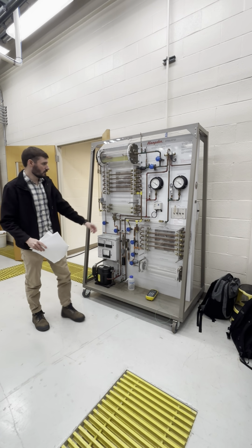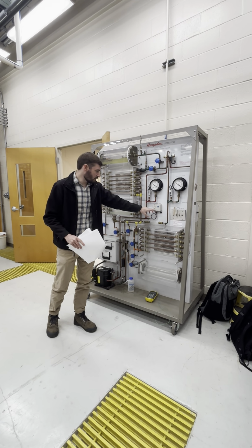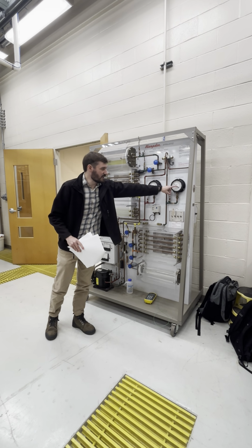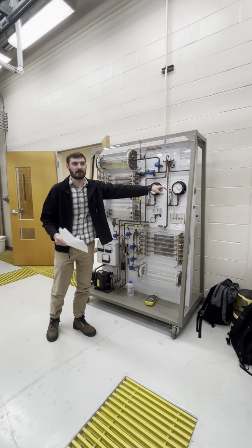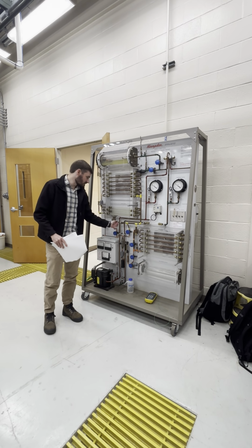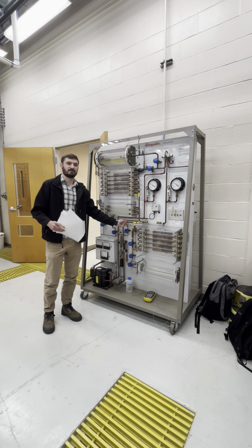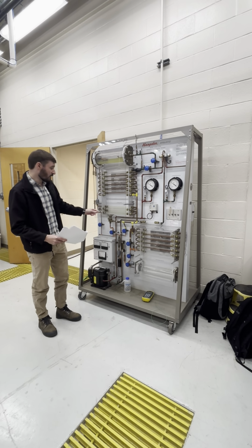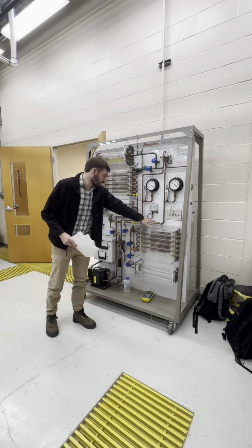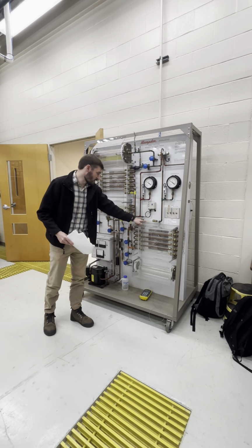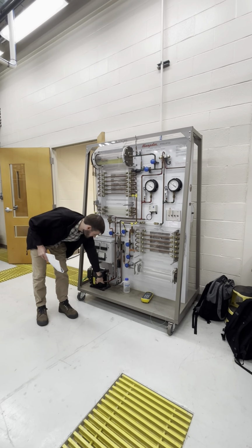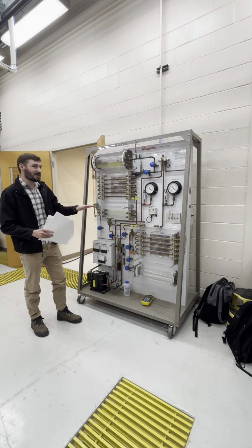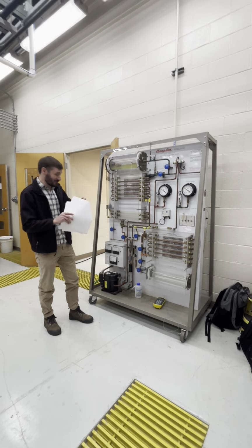You will crack them. There's a pressure shut off automatically at, I think, 27 psig. But if it gets to 25 and it's starting to go over, either shut it down or come tell me. If you see frosting on the expansion side, turn it off or come tell me. If you see a bunch of liquid just fully flowing out of here, this is the last stop before we get to the compressor inlet. Shut it off and then come get me. If you see anything wrong with the shut off, come get me.